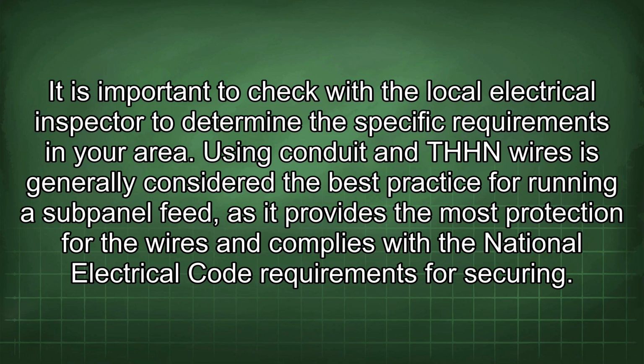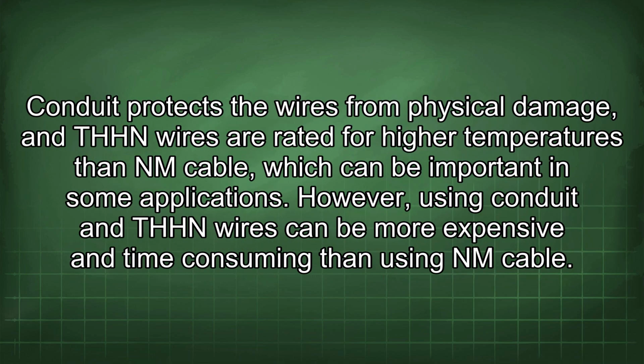Using conduit and THHN wires is generally considered the best practice for running a subpanel feed, as it provides the most protection for the wires and complies with the National Electrical Code requirements for securing. Conduit protects the wires from physical damage, and THHN wires are rated for higher temperatures than NM cable, which can be important in some applications. However, using conduit and THHN wires can be more expensive and time-consuming than using NM cable.